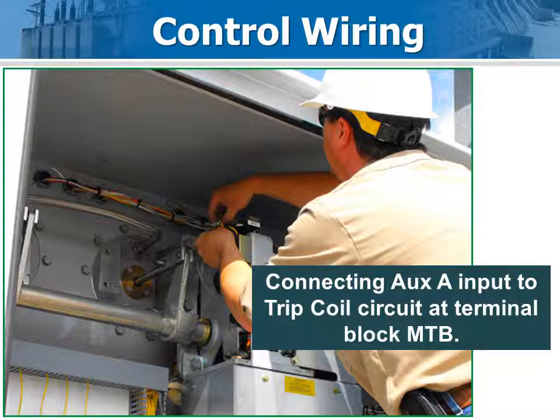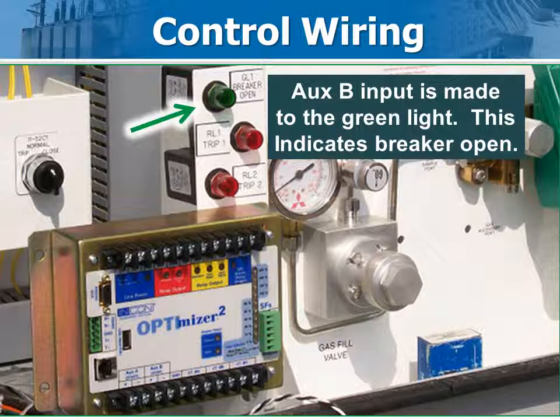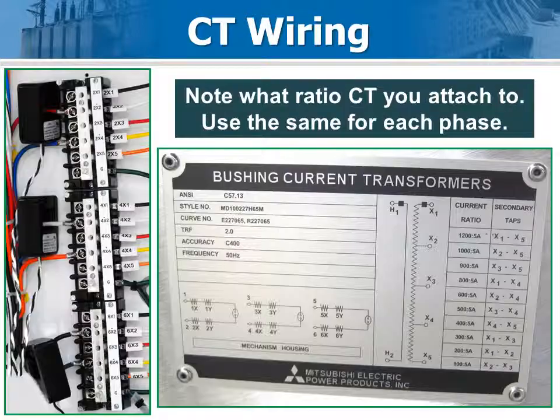Mitsubishi hides the trip coil terminal block above the mechanism. Check the prints to identify the terminals. Easy access to the green light makes it perfect to get at the 52B circuit. Identify the bushing CT circuits and place the current pickup coils around those conductors. This CT ratio, referred to 1, is programmed into the Optimizer 2 when you set it up.